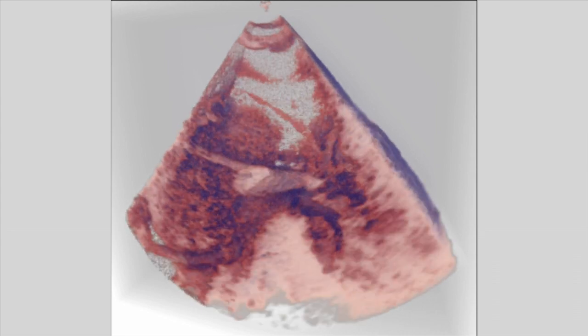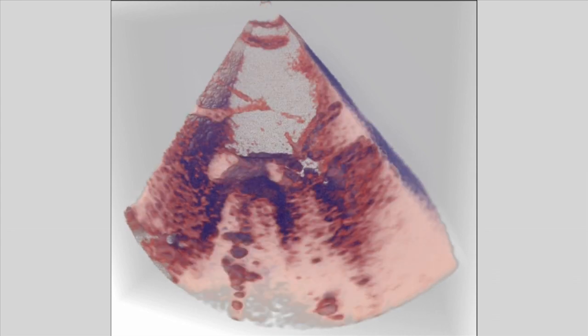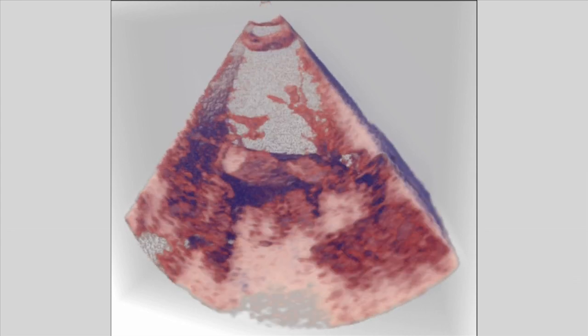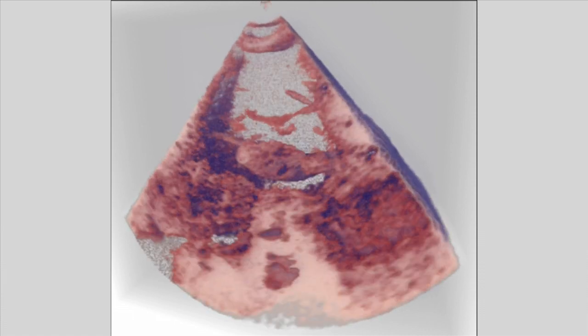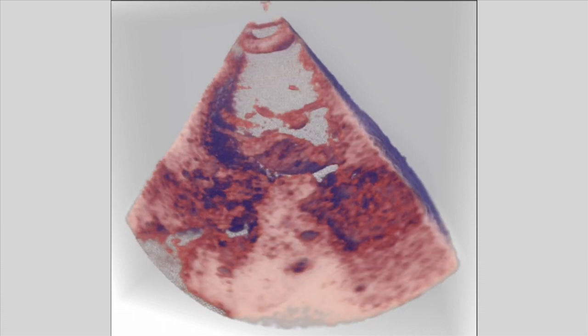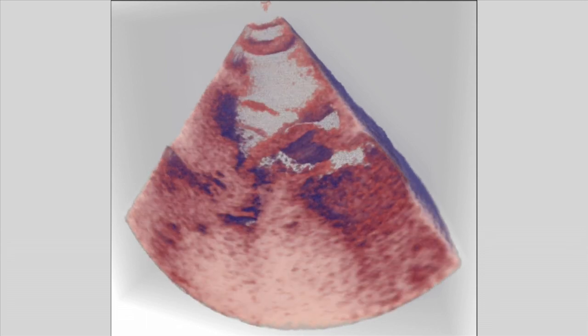The first is a streaming of ultrasound data in real time from a medical ultrasound scanner to a PC through an Ethernet connection. The stream contains both sample values and information about the geometry of the acquired volume, which makes it possible to reconstruct the volume on the PC side.